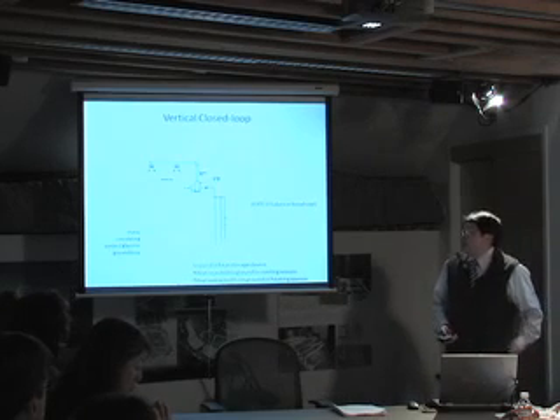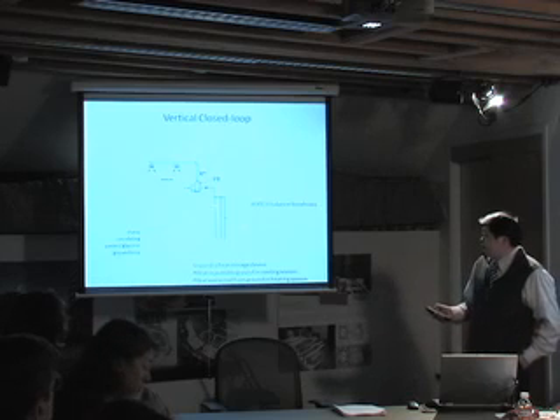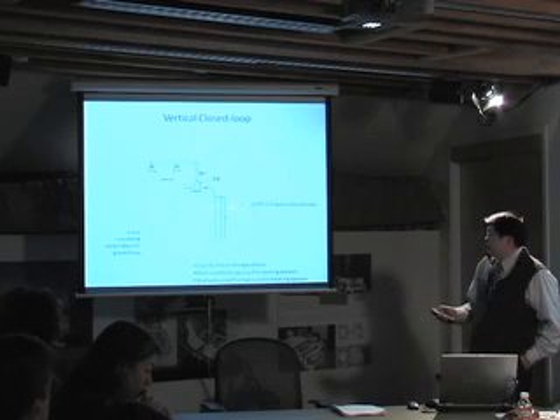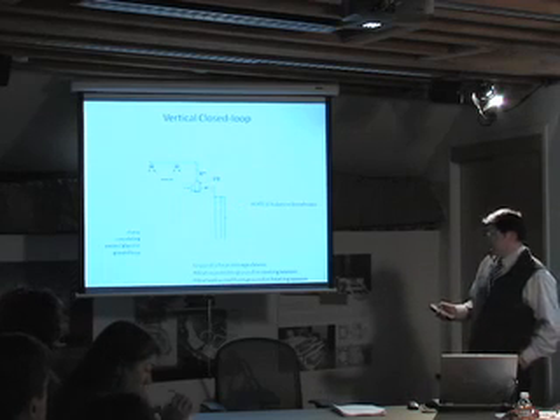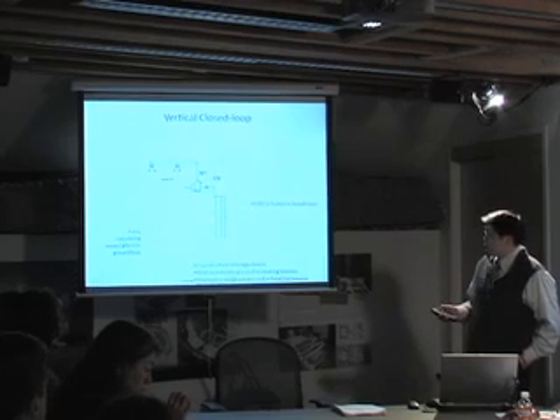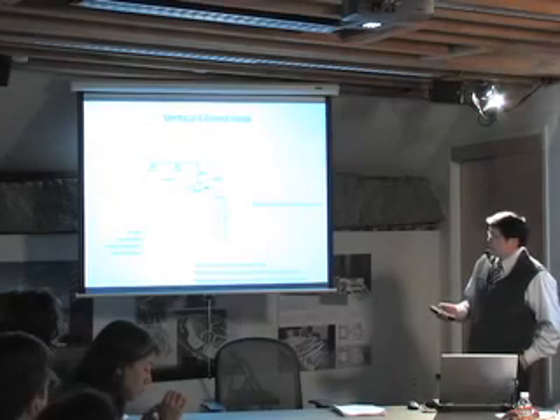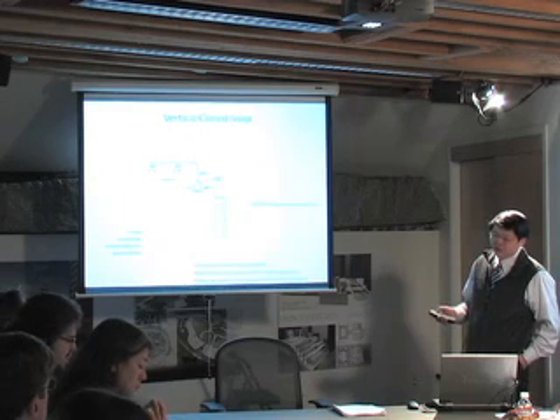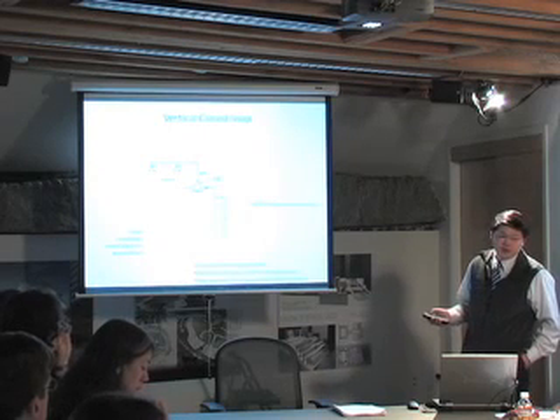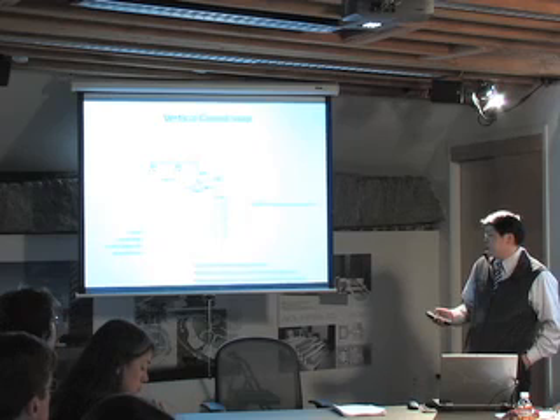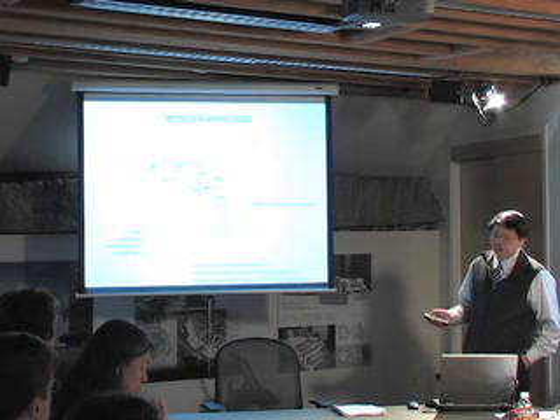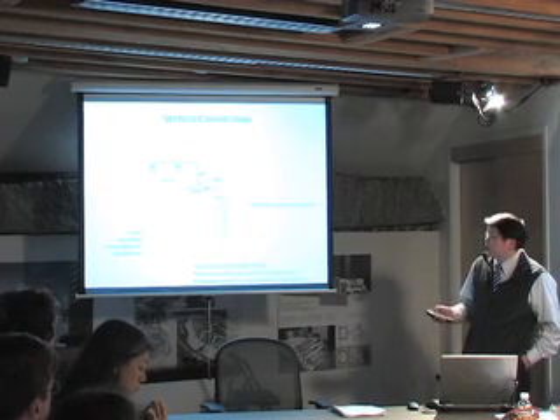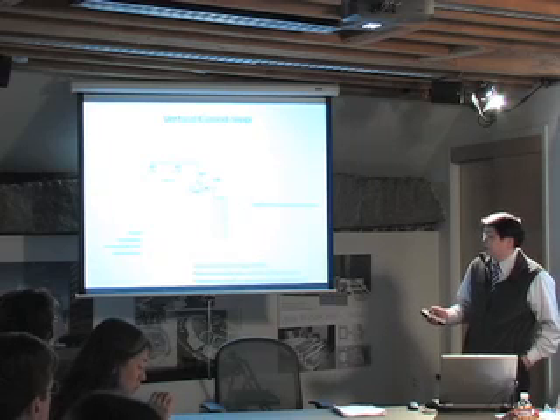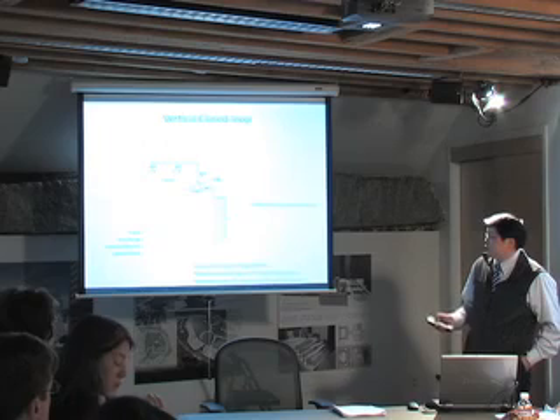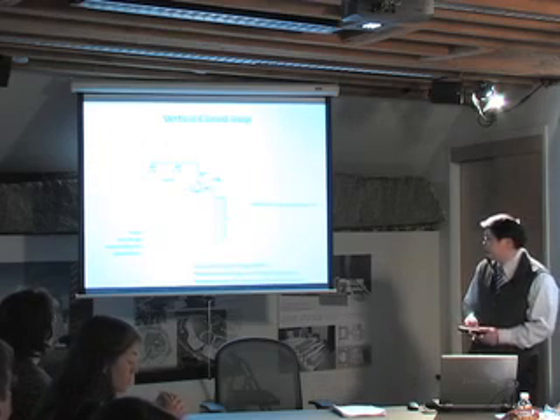Another configuration, vertical closed loop. Now, instead of burying the plastic pipes horizontally, you drill boreholes. Typically, could be 200 feet deep, 400 or 500 feet deep, sometimes even 600 feet deep boreholes. You can have 1, 2, or many of them, depending on the size of the load of your building. Same configuration here. You pump the water around and through the heat pump.